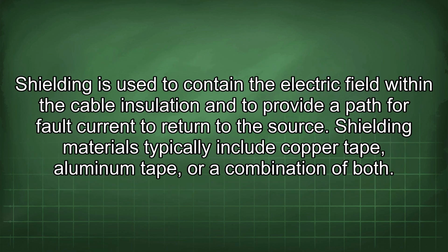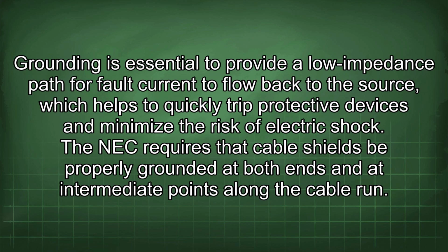Shielding is used to contain the electric field within the cable insulation and to provide a path for fault current to return to the source. Shielding materials typically include copper tape, aluminum tape, or a combination of both. Grounding is essential to provide a low-impedance path for fault current to flow back to the source, which helps to quickly trip protective devices and minimize the risk of electric shock. The NEC requires that cable shields be properly grounded at both ends and at intermediate points along the cable run.